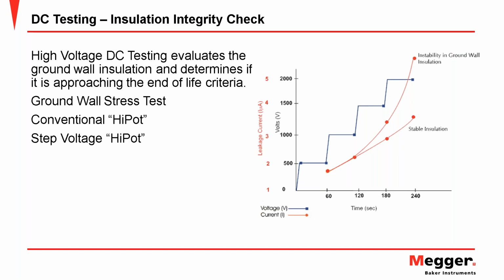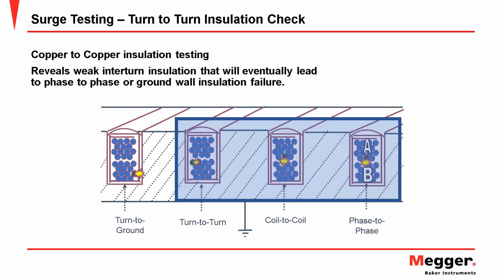And again, that departure from linearity is probably one of the most predictive indicators that our ground wall insulation system is starting to degrade. Okay. Now, another high voltage test that we do is called the surge test, and the surge test is valuable in that it looks at the copper to copper insulation, which is a different barrier.